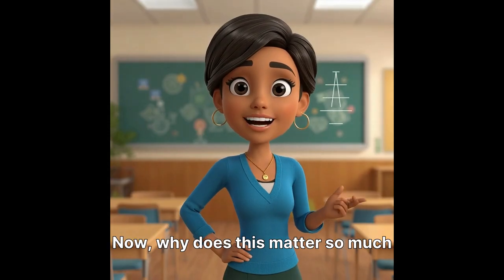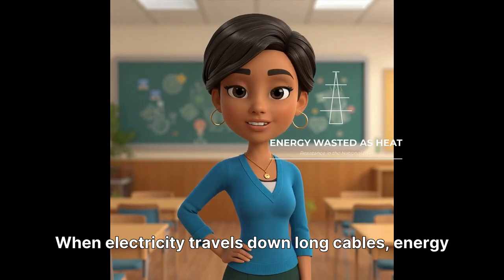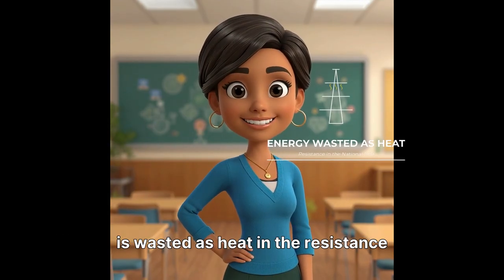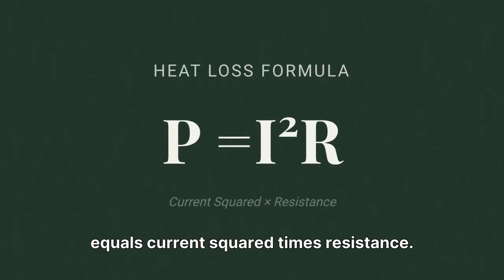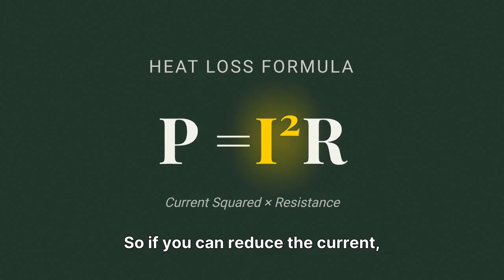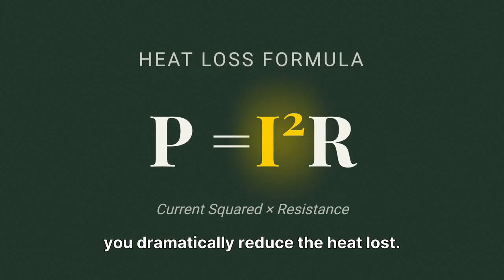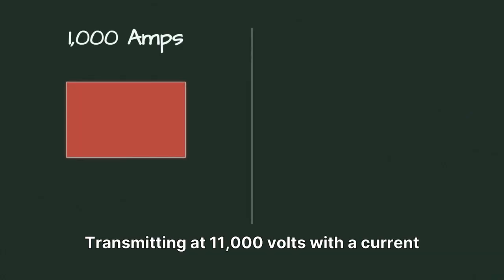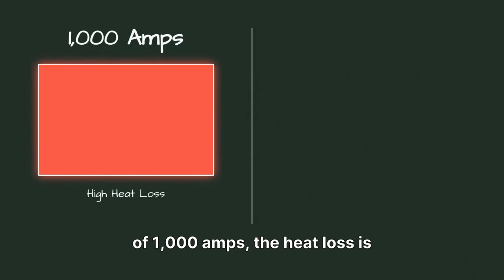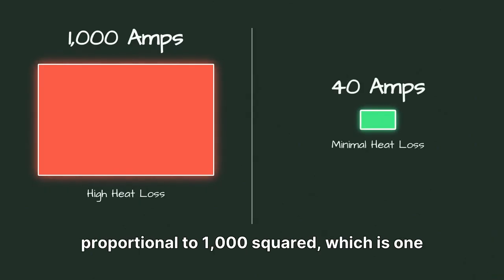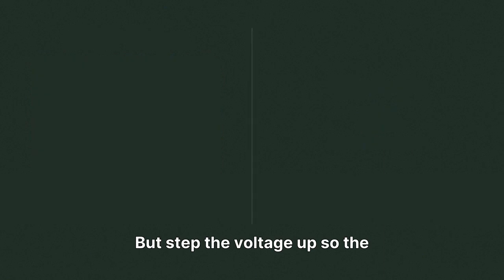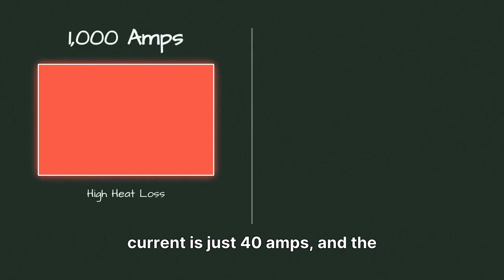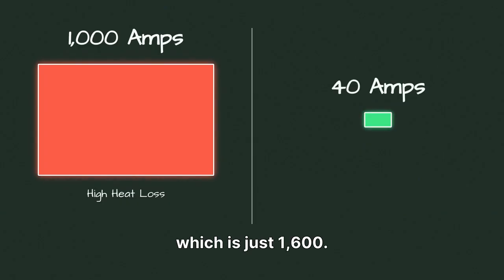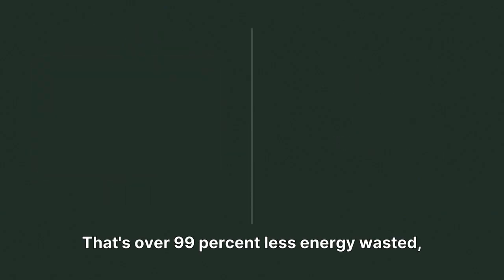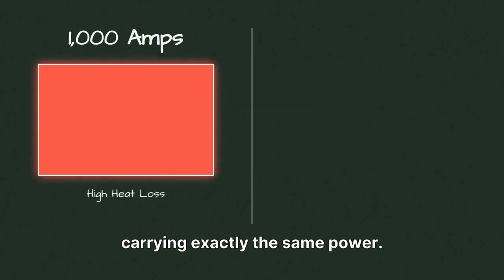Now, why does this matter so much for the national grid? When electricity travels down long cables, energy is wasted as heat in the resistance of the wires. And here's the critical point. Heat loss equals current squared times resistance. So if you can reduce the current, you dramatically reduce the heat lost. Let me show you. Transmitting at 11,000 volts with a current of 1,000 amps, the heat loss is proportional to 1,000 squared, which is 1 million. But step the voltage up so the current is just 40 amps, and the heat loss is proportional to 40 squared, which is just 1,600. That's over 99% less energy wasted, carrying exactly the same power.